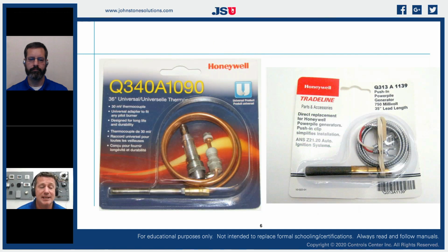And if we look at our packages, they actually tell us how much they generate. So the next time that you're looking at a thermocouple, just out of curiosity, take a look and see what it produces. If we look at the Honeywell Q340 series, I mean, those things have been around for decades. I don't know how many thousands of those I've put on in my lifetime. When I was doing service for residential HVAC, part of our service program was if it had a thermocouple on that piece of equipment, it got a new thermocouple because they were that inexpensive. So we included it as our service plan. So there were a lot of furnaces out there that got new thermocouples every year because it was an inexpensive component that served a critical part of the sequence of operation.